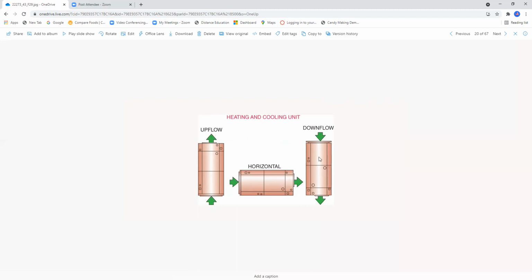A downflow heat pump system replaced what was a propane downflow furnace, and the person I was doing this job for did not like paying the very high price of propane that he had to fill in this large tank just away from his house in Port Orchard. And so he elected to go with a heat pump system, which was a good decision on his part. We're bringing in return air from the... there was originally a return air in the hallway. Then I put in another return in the living room in order to increase the airflow requirements.